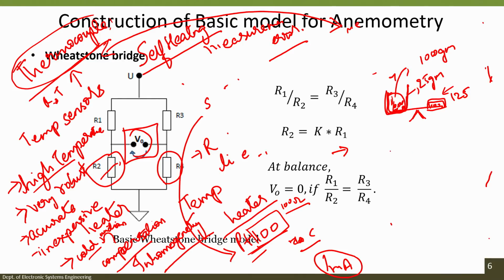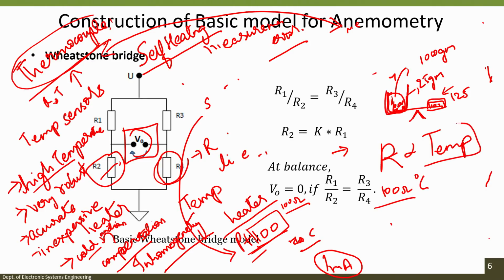In the same way, we have the temperature compensation, because the major application here is understanding the change in resistance based on your temperature change. Ideally, for instance, platinum 100 gives 100 ohm at 0 degree Celsius. However, when you're using it at room temperature, the temperature is around 27 degree Celsius. How do you compensate? It is no more 100 ohm. There is a variation. It could be 115 ohm. Who is going to compensate for this additional 15 ohm? So, if you want the bridge to be balanced, always make sure you use the compensating circuit.